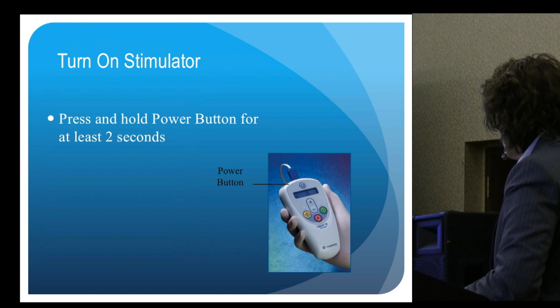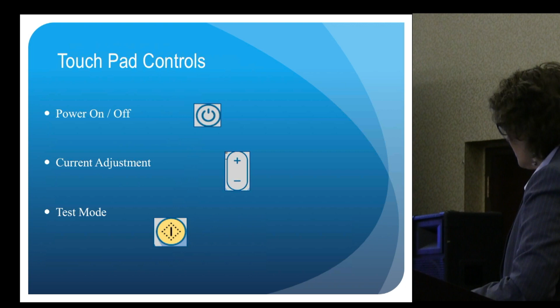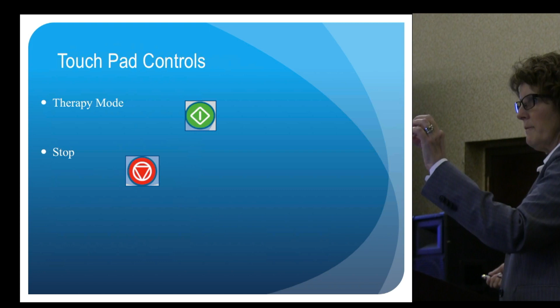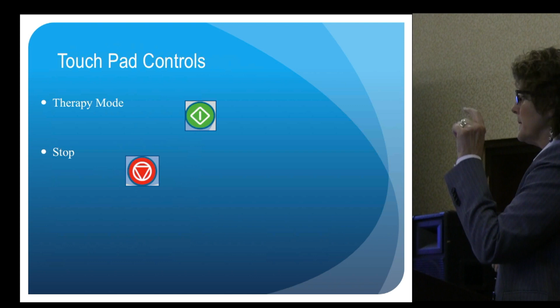Okay, so turn the stimulator on here. All right, 2 seconds. This is the power on, power off. This adjusts the current. This is the test mode is yellow. Therapy mode is green. Stop is red. So when you're going up, up, up, and you don't get a response and you want to put the needle in a little bit farther, you push stop, not green, stop. And then it'll take you back to 0, and then you'll start going up again.